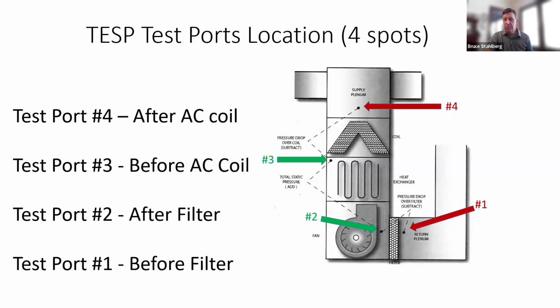There are 4 different spots that we do this. One is in the return ductwork before the filter. The second one is after the filter. The third one is before the air conditioning coil, if it exists. And the fourth one is after the air conditioning coil. So 4 different test ports.